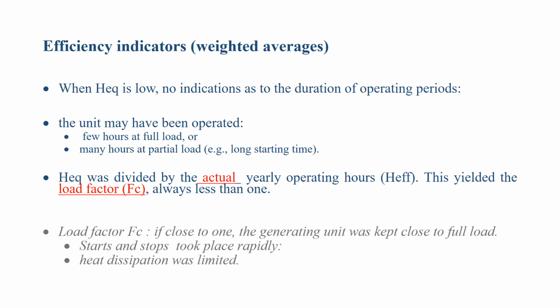Why partial load, for example? Because the starting time is very long for that unit, and there were several starts. So we don't know which of these occurrences is the true one - we need more information. That's why we also divided the equivalent operating hours number by the actual yearly operating hours. By the way, everything I say refers to one year, from the 1st of January to the 31st of December.